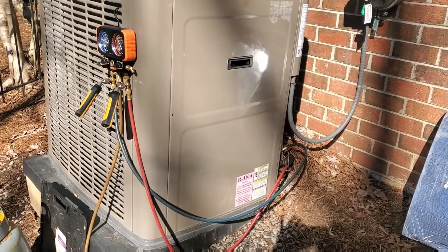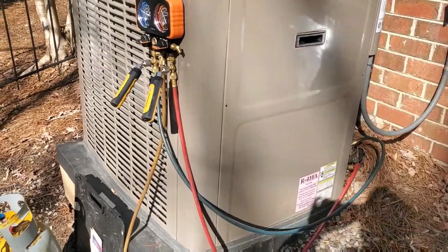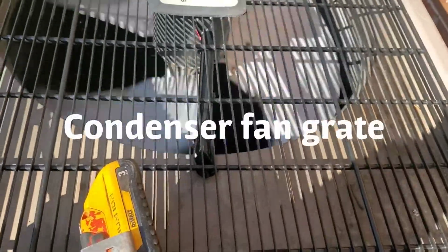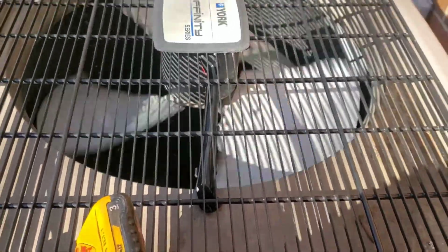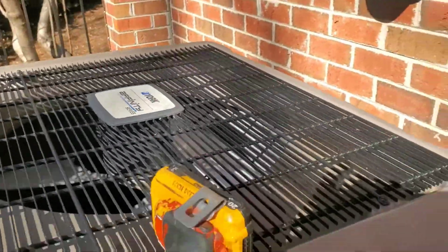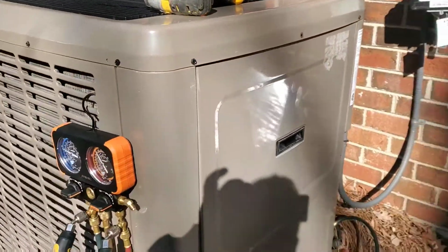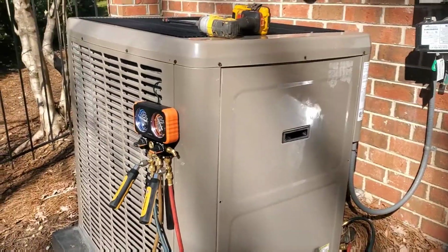And so how do you get suction line temperature? The easiest way to do it is just pop the screws off your condenser fan and just reach down in there and clamp your probe onto the true suction of the compressor. And just don't forget them when you leave. So it's really not that hard. You don't have to take the whole top of the unit off.